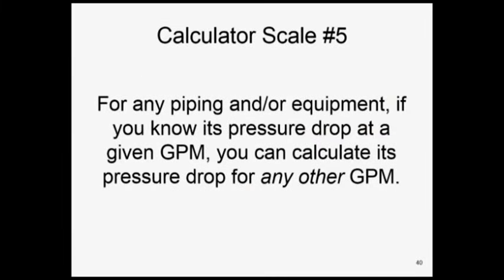So let's go back to the scale 5 or the square function thing we talked about. We talked about if I double the flow rate, my pressure drop's got to go up 4 times. If I cut my flow rate in half, my pressure drop's 25%. And I'm not trying to insult you, I'm just trying to get you familiar with that and what that means to you from a balancing standpoint. And that's all in the world at scale 5 on the system sizer, as we talked about. Or take your calculator out. If you got one hand, you don't want a system sizer, just plug in that function and see where we go with that.